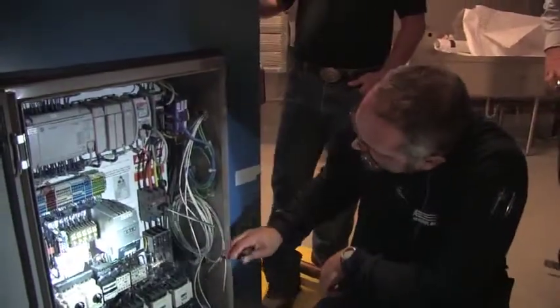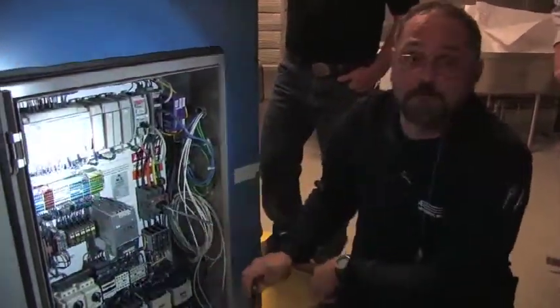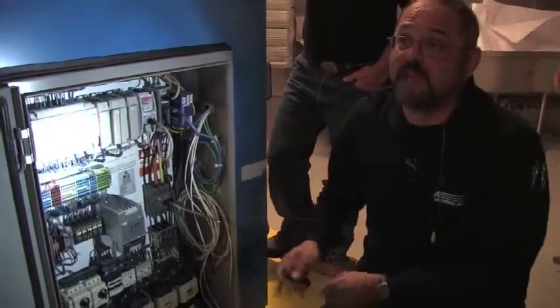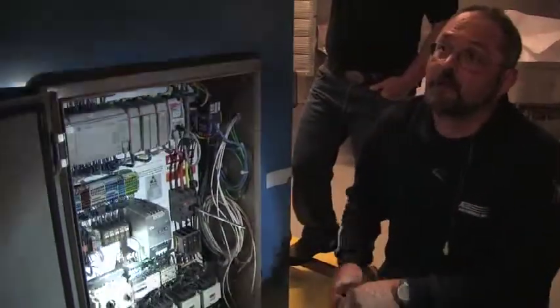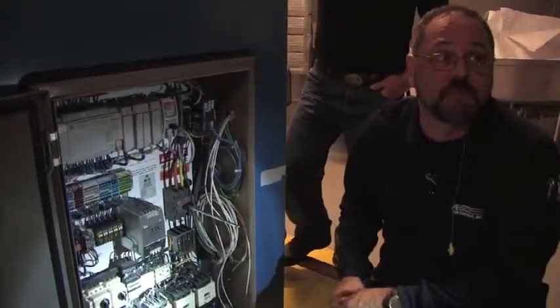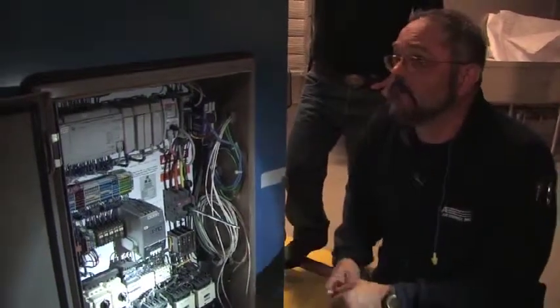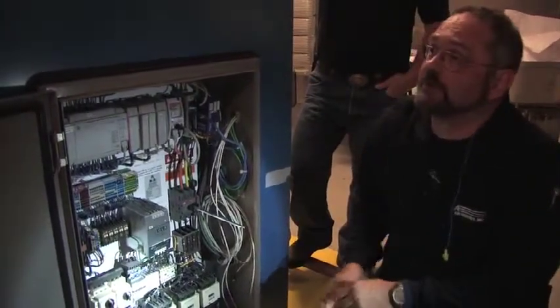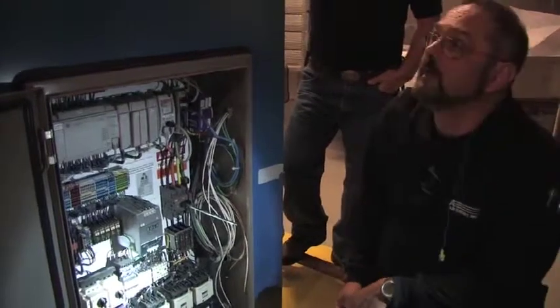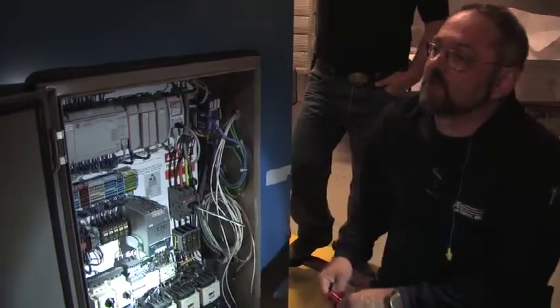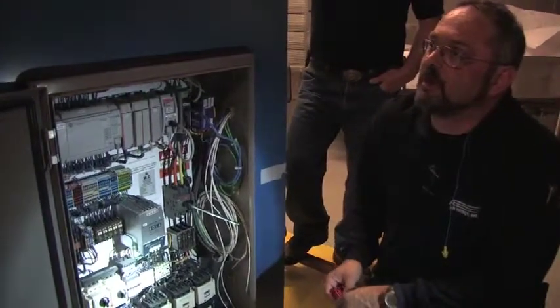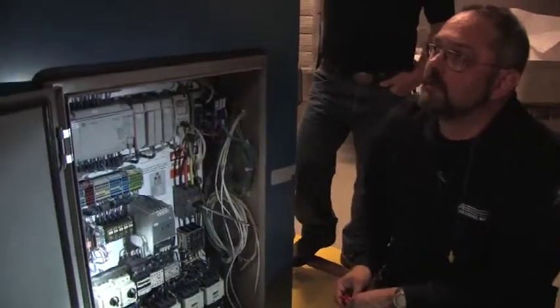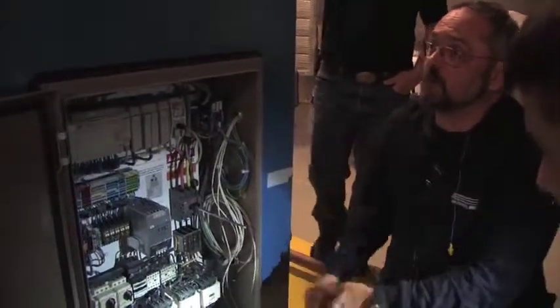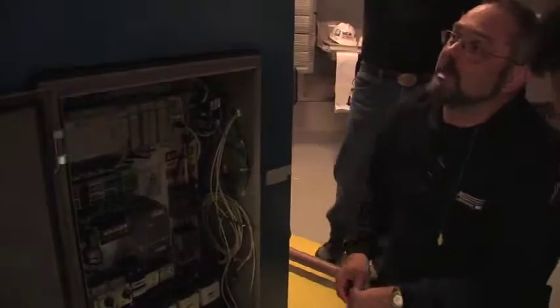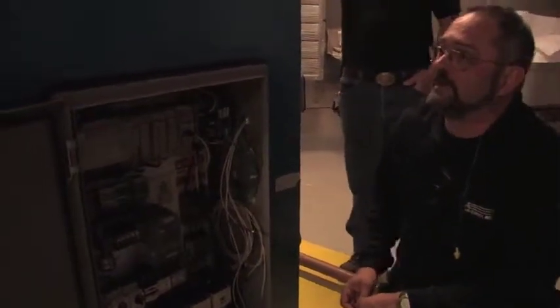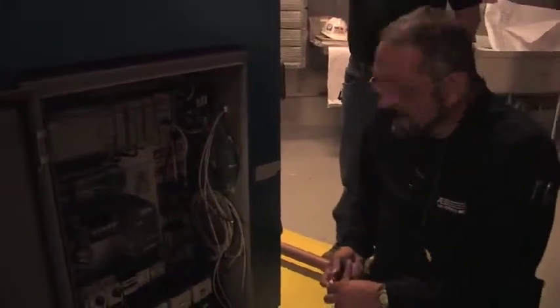Yeah. But an important point, that's true not only of these. Anything that's got a Y delta starter, the overload needs to be set at 58 to 60%. And you'd be amazed how often you open one up and... I mean, I get phone calls all the time. They ship the wrong overload on this machine. It's too small, because if the scale on the overload won't go to the full load, they'll call you up and say it's too small, I can't set it right. And it's like, yeah, you can set it right.